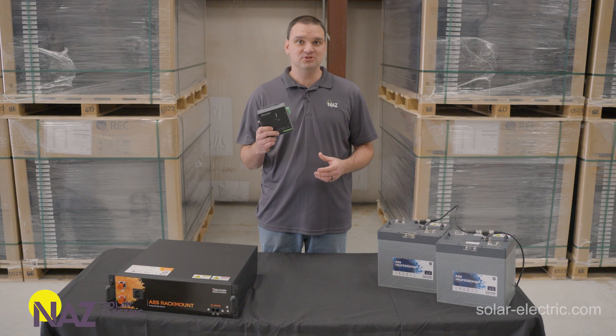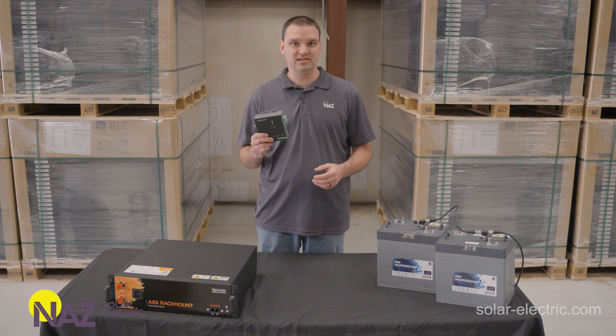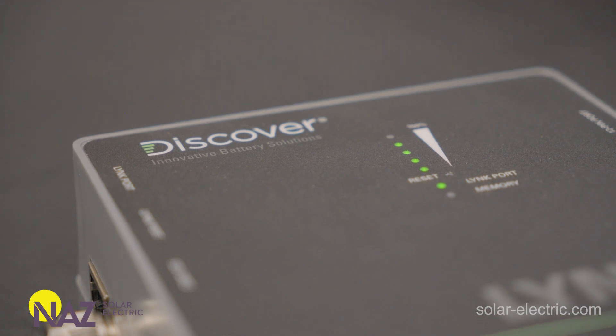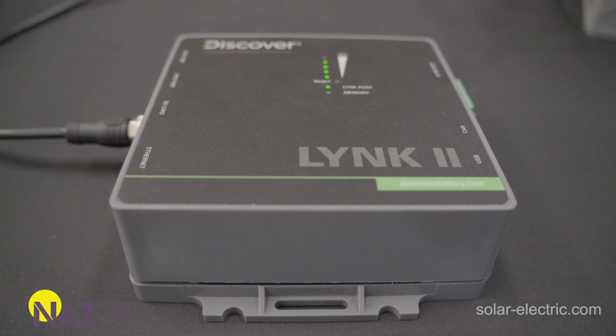Here we have the Lynk II from Discover. This is the gateway that allows the batteries to talk to various different inverter systems — just to name a few: SolarEdge, Victron, Schneider, and way more. The Lynk II provides various information to the inverter system: voltage, current, state of charge of the battery. It also provides target charging voltage, charging current limits, discharging current limits, and any other errors that the inverter system needs to know.